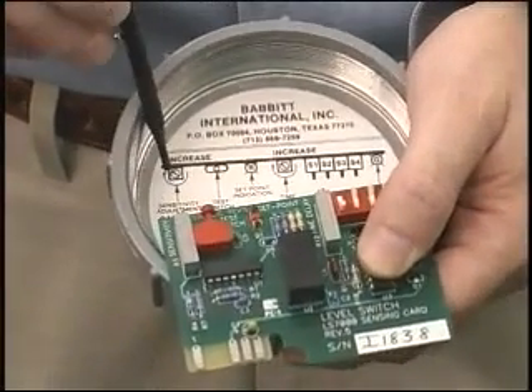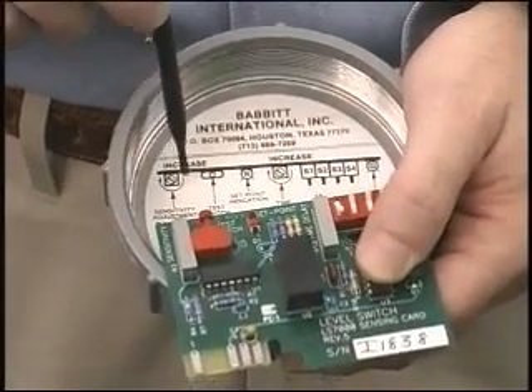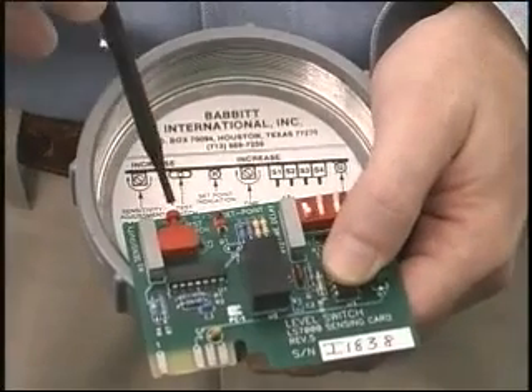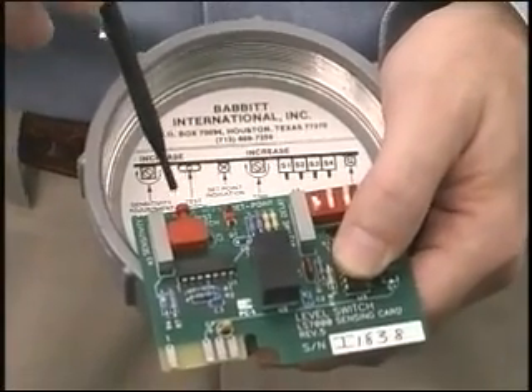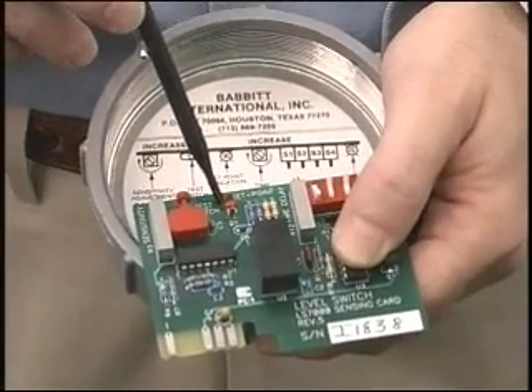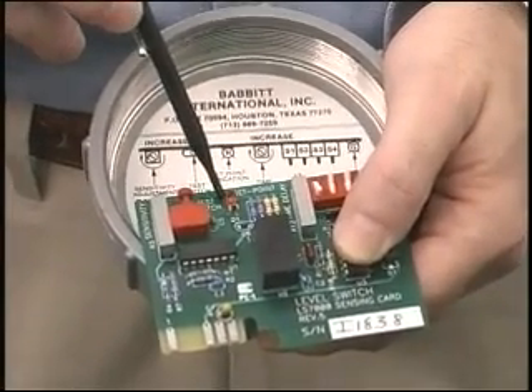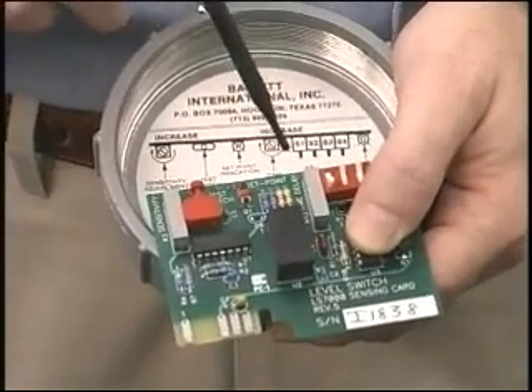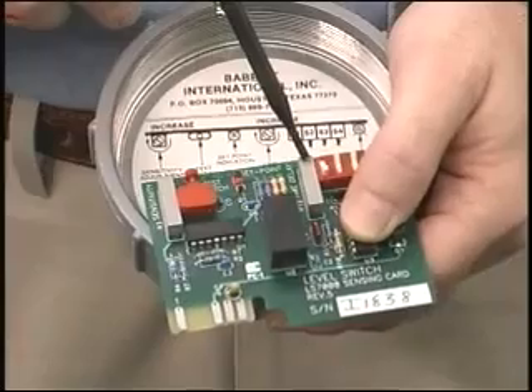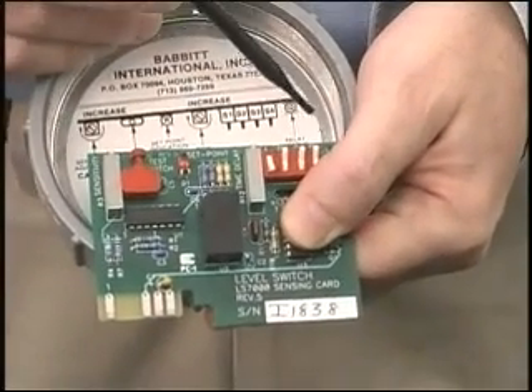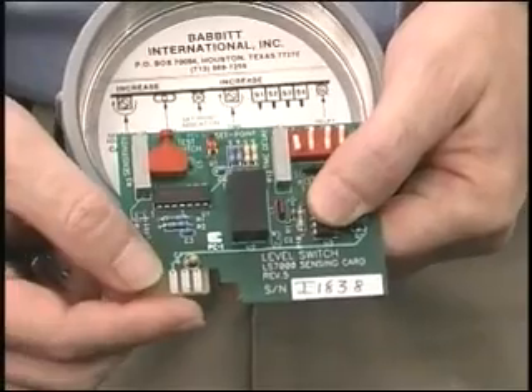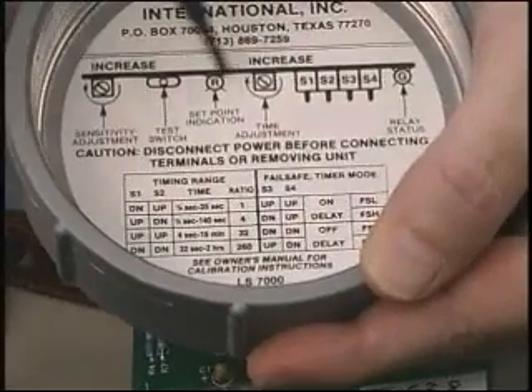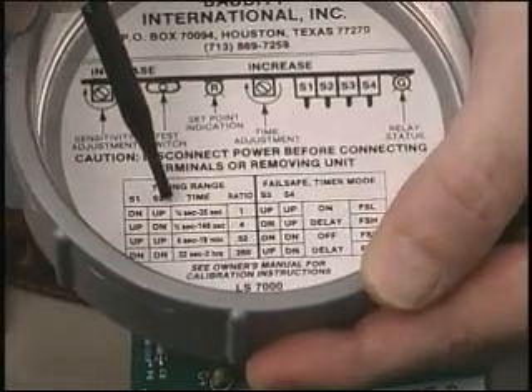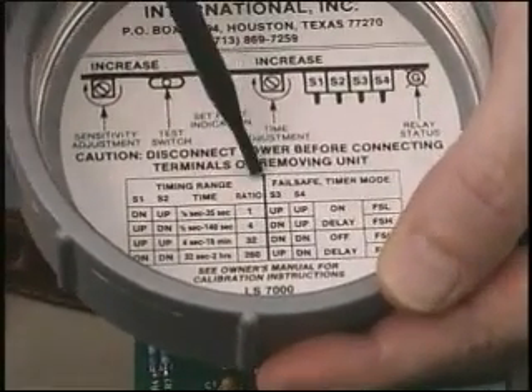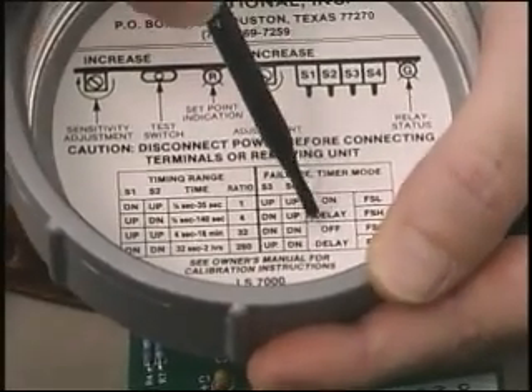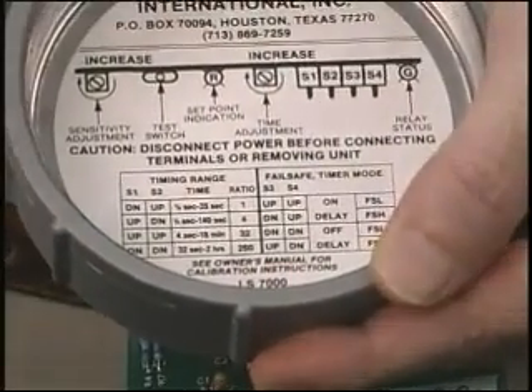This is the sensitivity adjustment, and what our shorthand here means is you turn it clockwise to increase the sensitivity of the unit. Next to that is an onboard test switch to test the circuit. The red LED tells you if material is touching the probe, and this is what you watch when you're calibrating the unit. There's a time delay adjustment. Again, you turn it clockwise to increase the time. A green LED over here is a relay status. When the green light's on, the relay is energized. And these dip switches are explained in this chart. S1 and 2 select a timing range from 1/8 of a second to 2 hours, and S3 and 4 select on or off delay timing, fail-safe low or fail-safe high operation.